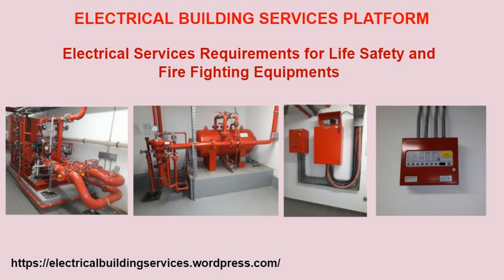Number 11, both the primary and secondary supply to the life safety installation need to be sufficiently protected against fire and water damage and also separated from each other so that the failure of the cable or equipment, either by mechanical breakdown or damage by fire in any one system, does not affect the other supply. Number 12. Protection against fire may be achieved by choice of cable, choice of route, for example, through protected area or external to the building, or by the provision of additional fire protection. Number 13. The fire procedure of the building should not include the isolation of circuit supplying power to the above mentioned equipment.